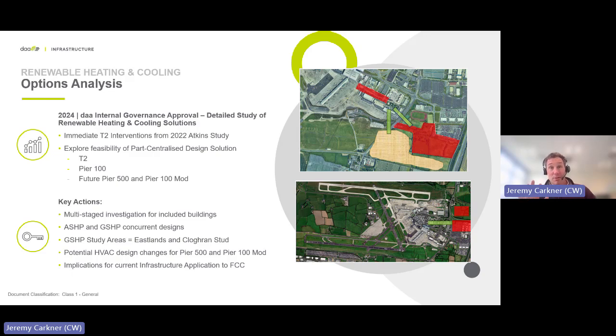The idea was to look at geothermal in those four areas, the three reds and the amber, and also concurrently look at air source, so do a real optioneering exercise. The air source heat pumps would be directly adjacent to the building, the terminal, and Pier 100. With geothermal, we were potentially having to make some design changes to the heating and ventilation strategy for both Pier 500 and Pier 100. That was part of the original plan.